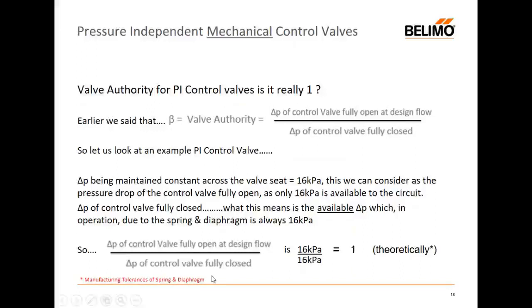The reason that I say theoretic is that if it was 1, it would be perfect, and few things in life are. So we have some small manufacturing tolerances. The spring, the commercial spring in the valve controlling the diaphragm, has a P-band, which depending on how it's being compressed, will have a plus minus, and that can vary according to spring manufacturers. And the diaphragm is a soft EPDM device, which again will float a little bit as it reassumes its new position if there's a change in pressure. So we can say 1 in theory, but in reality, it's close to 1.